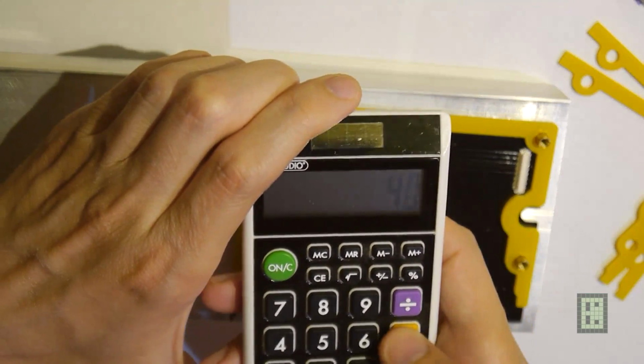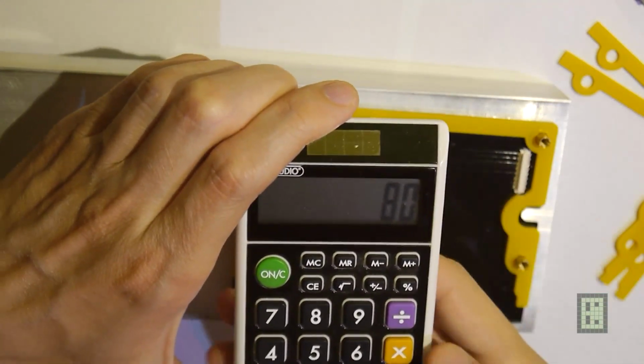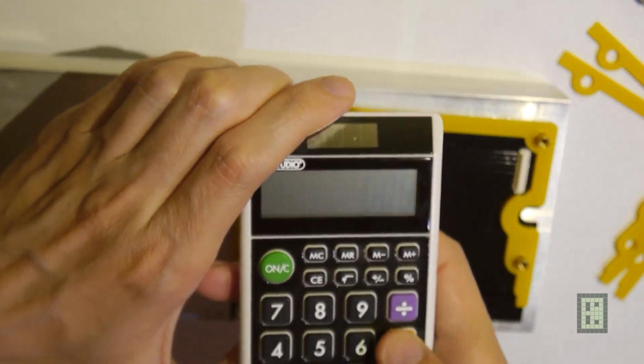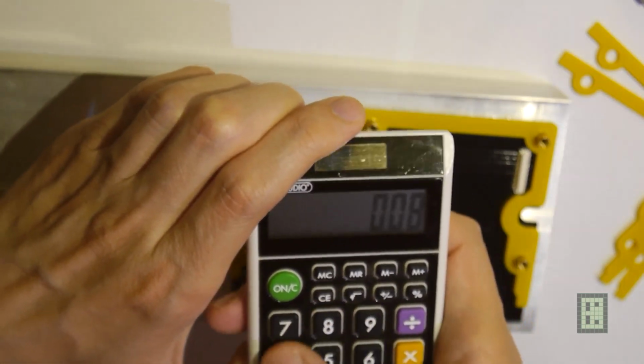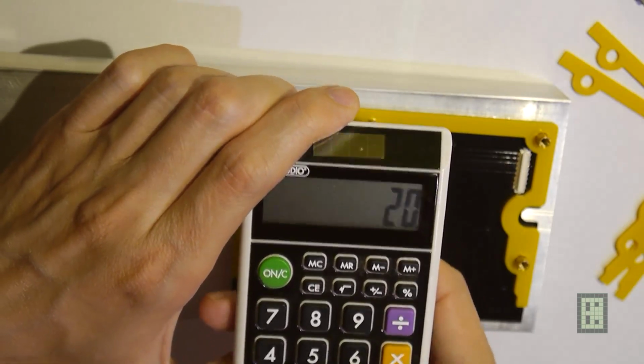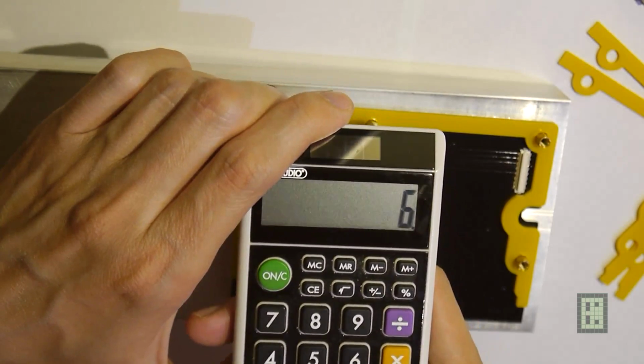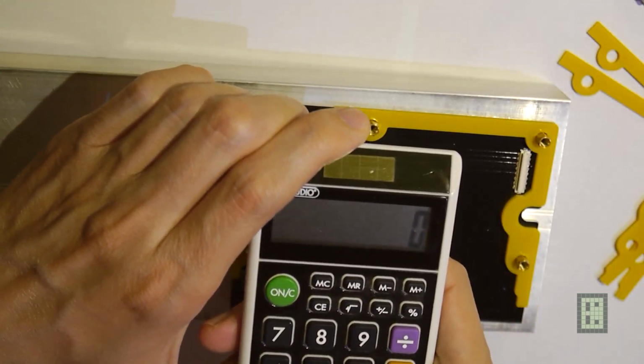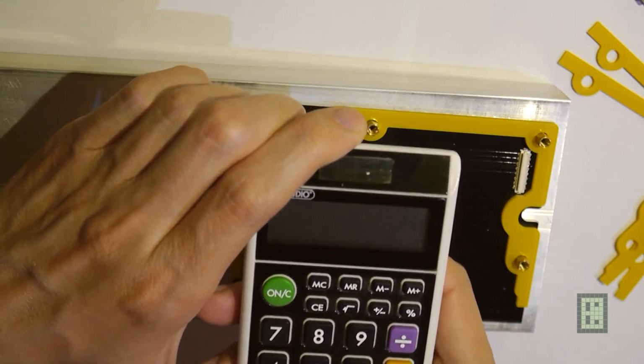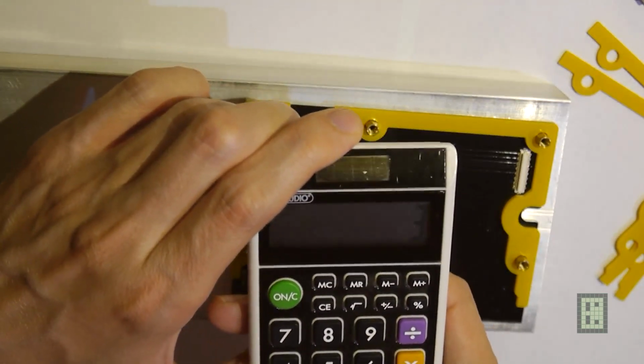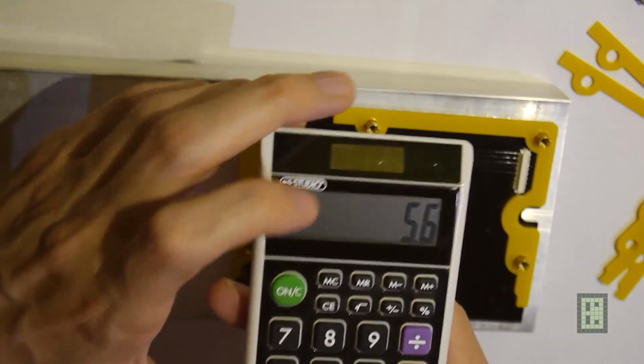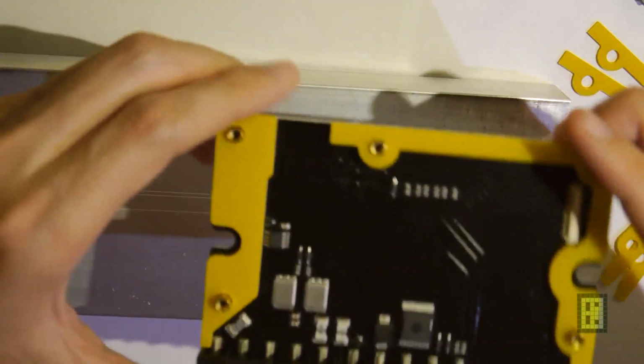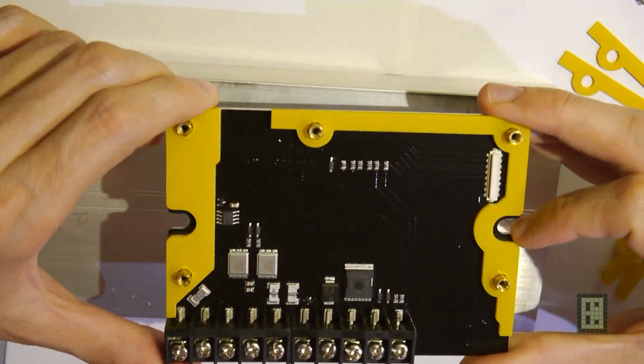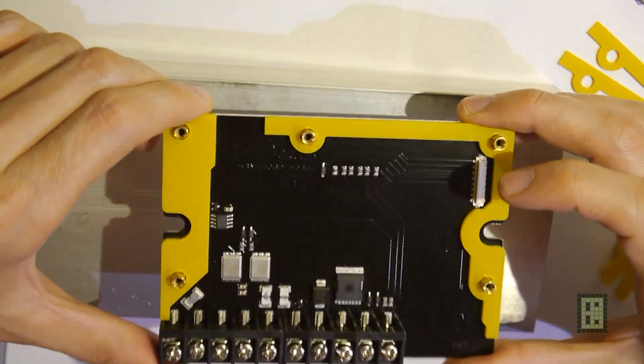To show you that's the case: 40 amps discharging multiplied by 2 milliohms is 80 millivolts, so 0.08 multiplied by 40 amps is 3.2 watts on the load side. Then 20 amps charging multiplied by 6 milliohms gives 120 millivolts, so 0.12 multiplied by 20 is 2.4 watts. That's 2.4 plus 3.2, so 5.6 watts, just under the 6 watt limit I was talking about. So this can do 20 amps charging and 40 amps discharging without any additional heat sinking.